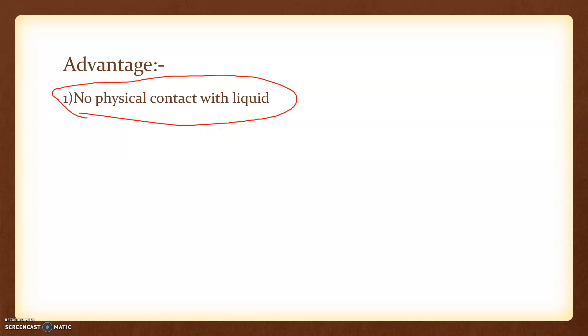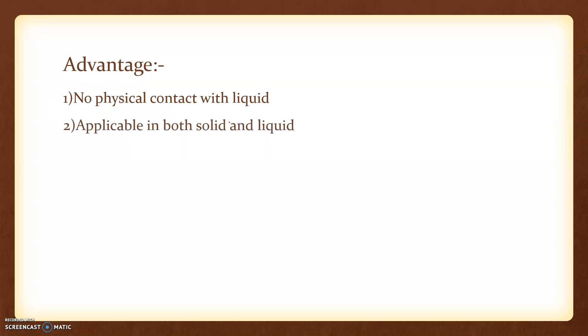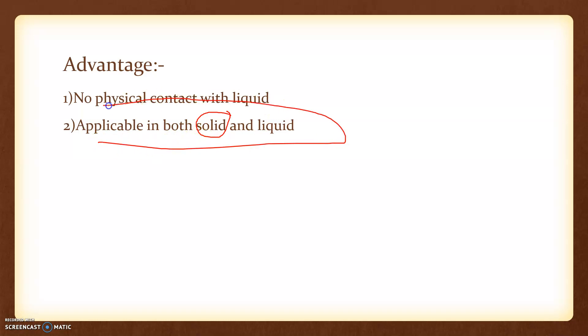So the major advantage of the ultrasonic sensor is: there is no physical contact with the liquid. Another very interesting advantage is that it is applicable to both solids and liquids. With a capacitive sensor, using parallel plates in a solid is difficult — the plates may get scratched, may break, and the gap between the plates may also change. So a capacitive sensor is not a good idea for measuring solid levels, whereas the ultrasonic sensor is situated above the container and does not come in contact with the solid or liquid at all.